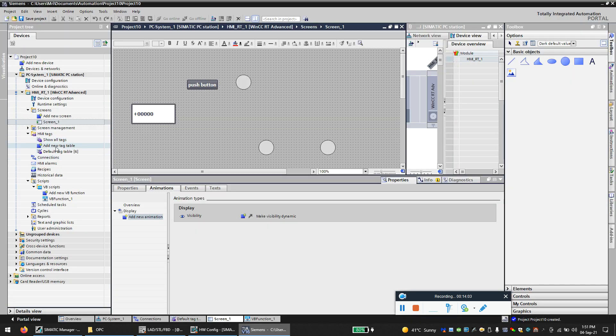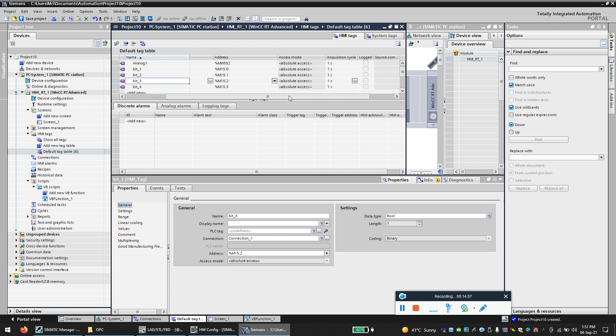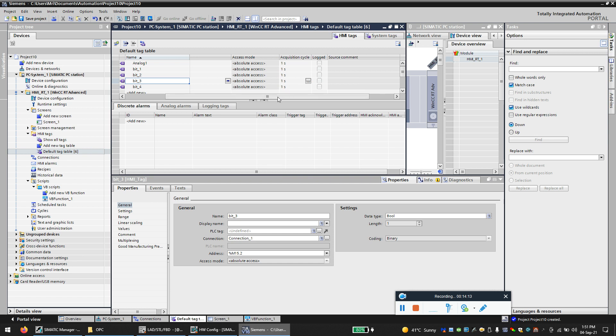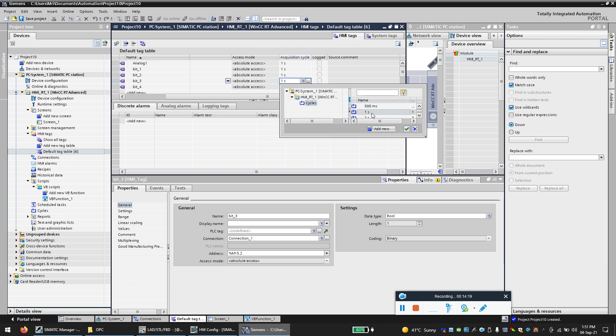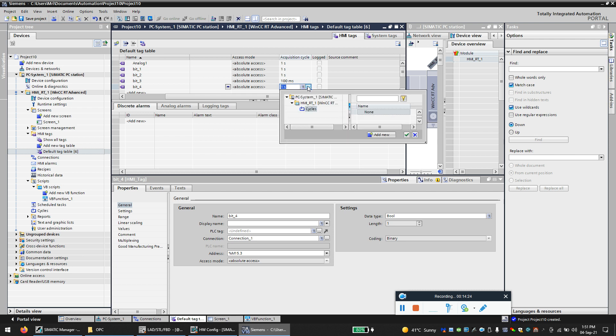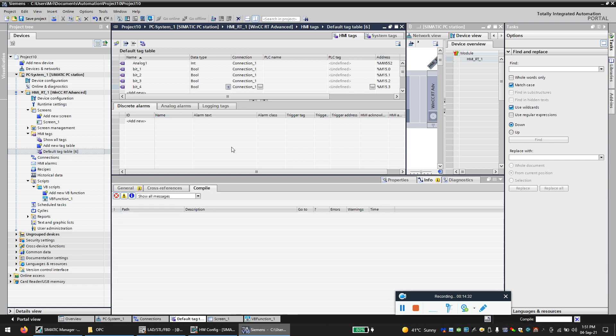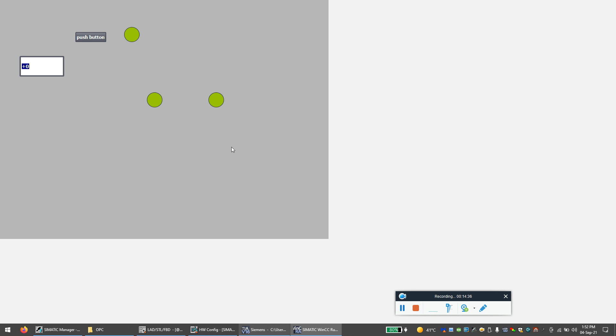One thing you need to be careful is that you can see this data acquisition cycle. It means every one second WinCC is updating the value from the PLC. But our bit is sent every 500 milliseconds, so I need to make this less than 500 milliseconds. So I'll keep it at 100 milliseconds. So now we'll run and see.